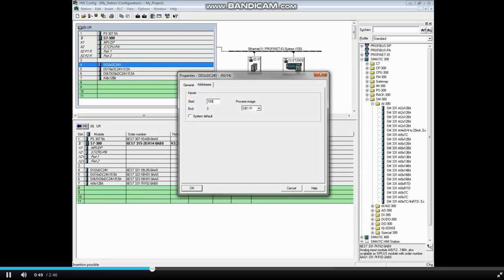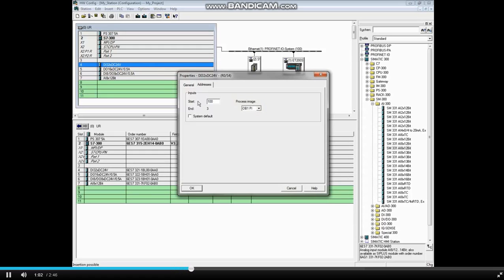The module will now occupy input bytes 100, 101, 102, and 103. You should not change the process image from OB1 unless you are sure what that entails. You can find out more about process images in the help file. Click OK.